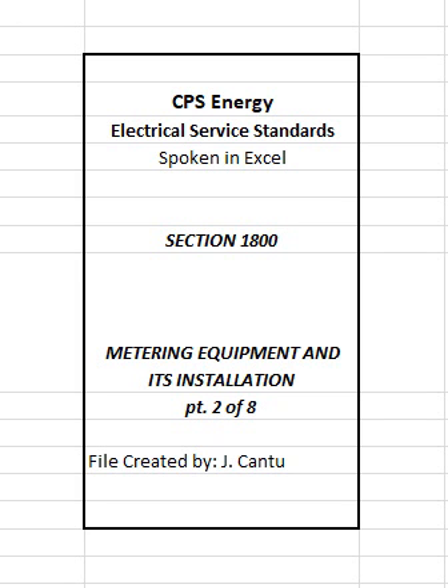On overhead to underground services, CPS Energy will furnish the line-side conductors. All connections must be made in the instrument transformer enclosure to establish the point of delivery, POD. Refer to Figure 1813. 1. Where cable-to-cable connections are required, they shall be made on the load side of window-type CTs.